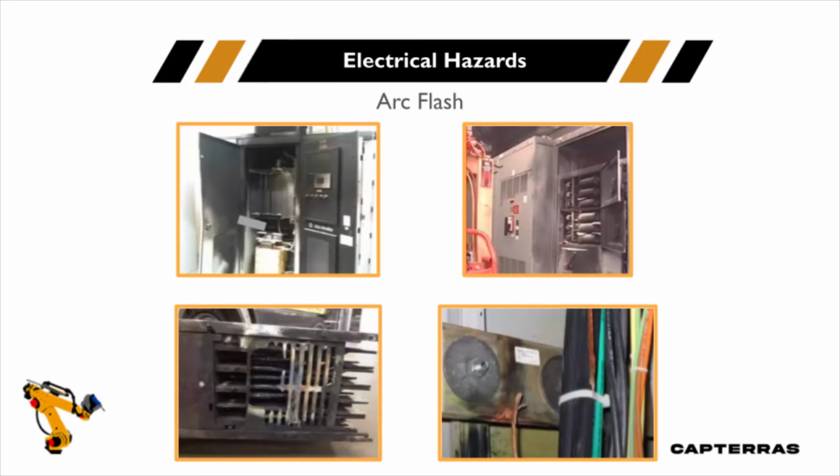No one was working on it, but the gentlemen that were standing in the room, three of them standing about 10 foot away from this, actually said the flames came out to just about where they were standing. Fortunately, no one got hurt, but they were, no pun intended, totally blown away that they weren't even working on it, and the arc occurred, and the flames came out so close to where they were standing. So they do infrared scans on this once a year. Now they're going to do these infrared scans every 6 months to try and help avoid something like this. They don't know the actual cause of this explosion.